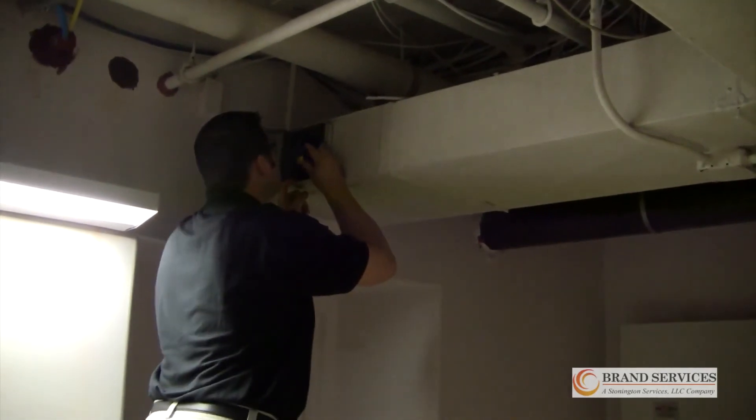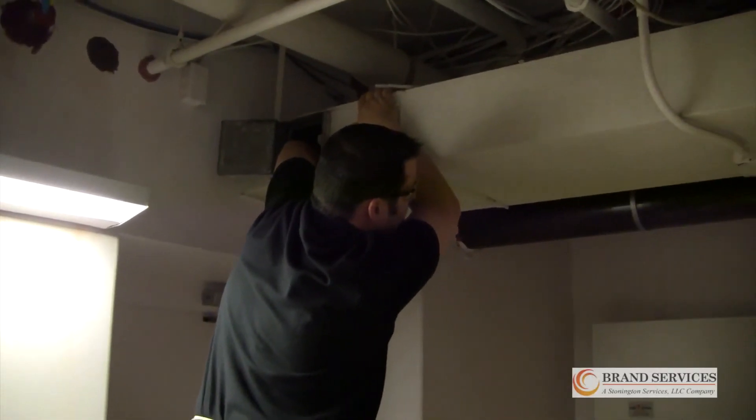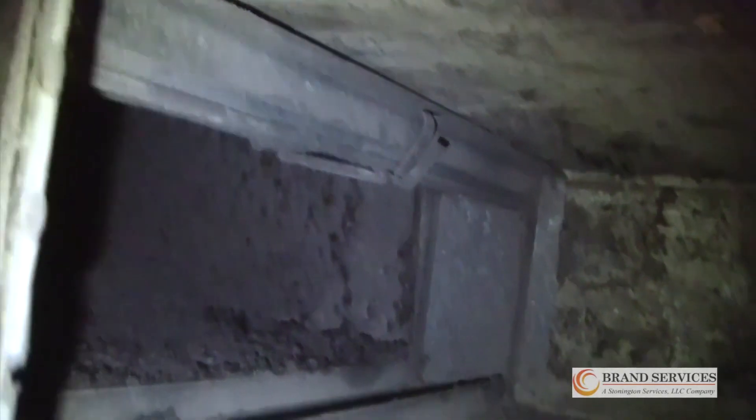Sometimes in your hospitals, we will find dampers closed. This is what a closed damper would look like. Technicians will reset your fire damper. All tests shall be completed in a safe manner by personnel wearing personal protective equipment. Here is what your damper will look like reset.